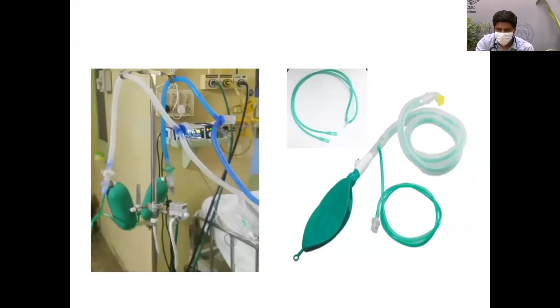So we can start off with 15 liters of oxygen in a patient who is coming with severe ARDS, and as the oxygen requirement is coming down, here is how to convert a Bains into oxygen conserving modalities. As you can see, there is a Y connector here. You can connect the Y connector to the Bains circuit and connect one limb to the oxygen flow meter and the other to a medical air flow meter. In that way, we can maintain the flow and adjust the FiO2 from the oxygen port. In this way, we can conserve the oxygen.